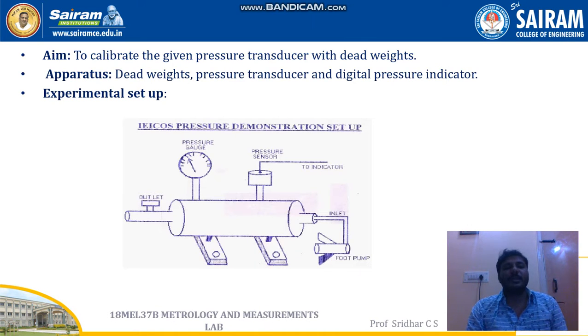First, the main aim of this experiment is to calibrate the given pressure transducer with dead weights. That is, with the given weights we're going to calibrate this pressure transducer. The apparatus we require is dead weights, a pressure transducer, and a digital pressure indicator. This is the equipment required in order to calibrate the given pressure transducer.